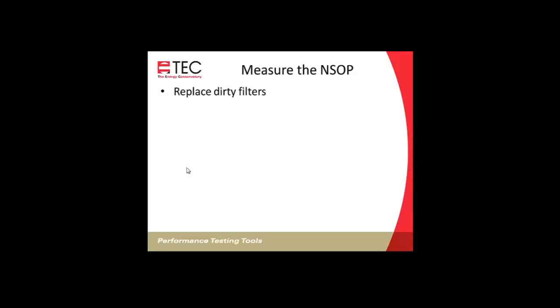So like with the True Flow, we will first replace the dirty filters. We'll open all of the registers. We'll open a window because if the Duct Blaster or the air handler fan changes the pressure in the room, we won't get an accurate reading, because we're reading operating pressure with reference to the room. If we change the room pressure with the air handler running, we're not going to get an accurate reading. We'll open the air handler zone to the outside. If we're in a crawl space or an attic or a garage, we'll want to open that space to the outdoors.